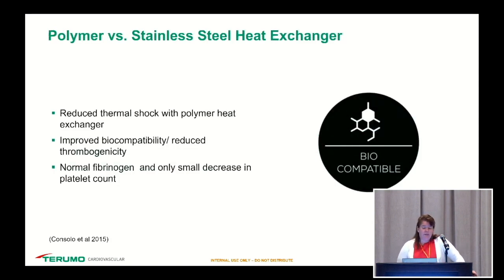So the polymer versus the stainless steel heat exchanger: the reduction of thermal shock in the polymer heat exchanger, thermal shock being that the stainless steel is going to warm and cool your patient on the surface, whereas these polymer fibers are going to actually warm and cool the blood throughout the entire fiber itself. So that helps with the potential of thermal shock. So we have improved biocompatibility, reduced thrombogenicity, and we have normal fibrinogen, and only a small decrease in platelet count is what this multi-center study showed.